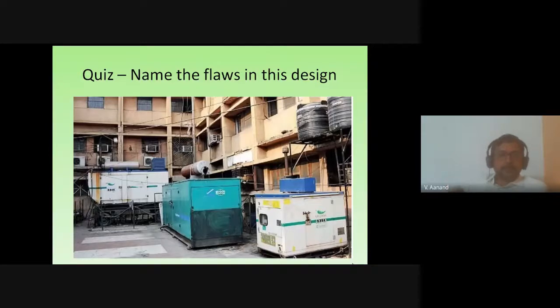And second, as rightly pointed out, the ventilation, the cables dangling around, everything has to be looked into. What about the pollution control board regulation, and where have I taken the exhaust vent up to the terrace level? How am I going to maintain the farthest generator, how do I pull it out for maintenance? Can you see my cursor? Yes. If all-round maintenance is warranted around this generator, the clearance between the building and the generator is very pathetic. There's no way a person can access it properly; this generator is supposed to be mounted at floor level height, like this one.